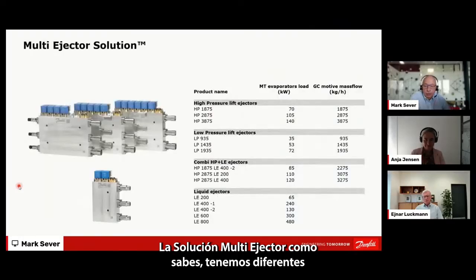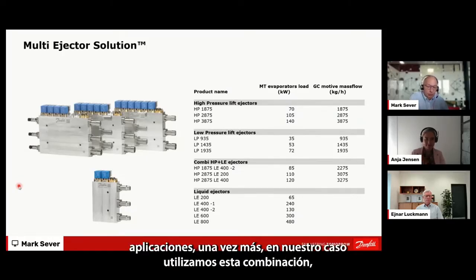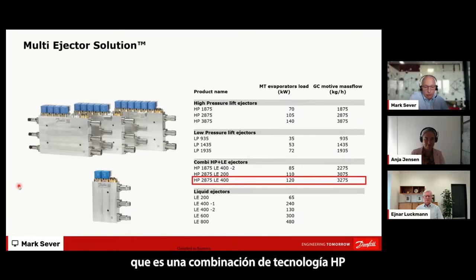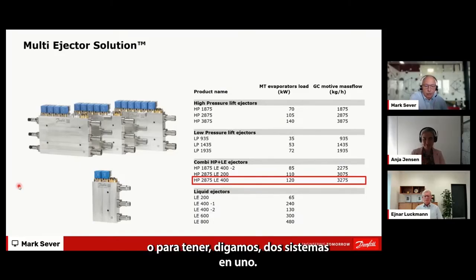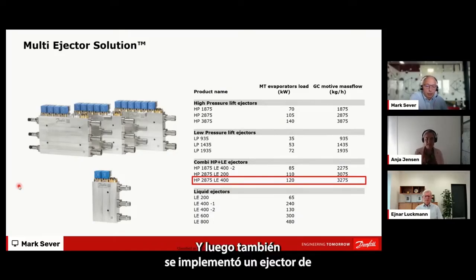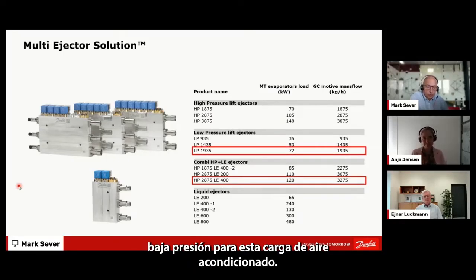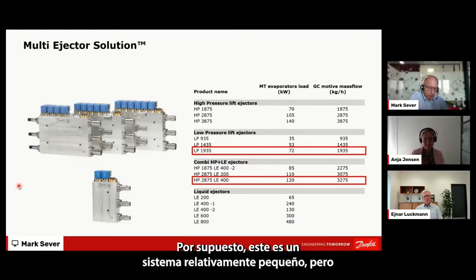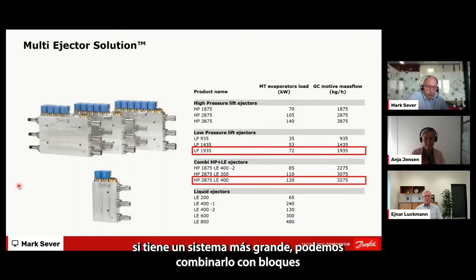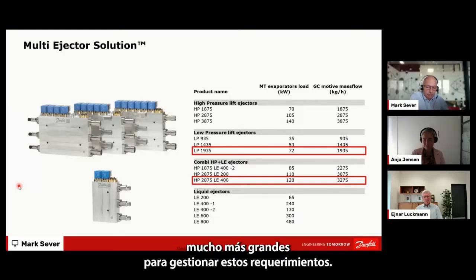Multi-ejector solution, as I mentioned, has different versions in our portfolio depending on the application. In our case, we use this combi ejector, which is a combination of HP technology and liquid ejector technology, essentially two systems in one. There's also a low pressure lift ejector implemented for the air conditioning load. This is a relatively small system, but for bigger systems we can combine much bigger blocks to manage these requirements.